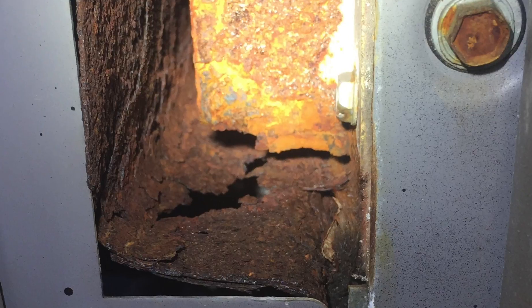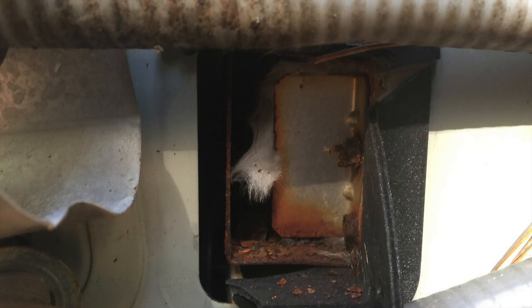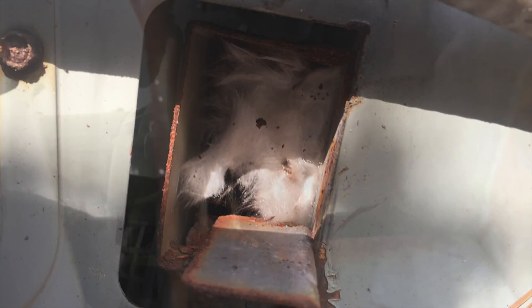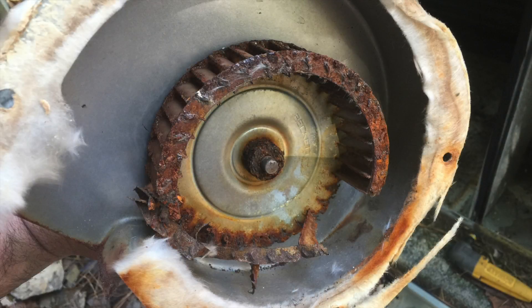With the beginning of the 2016 heating season here in North Carolina, we've had a plethora of failed inducer motors over the past week — everything from bound-up motors to rusted-out motors to broken wheels, and the occasional mysterious hot spot on the heat exchanger.